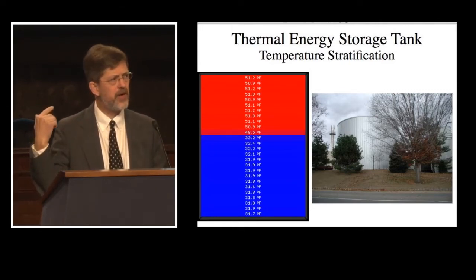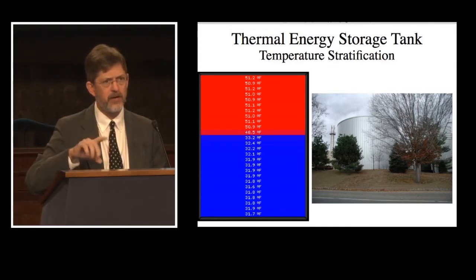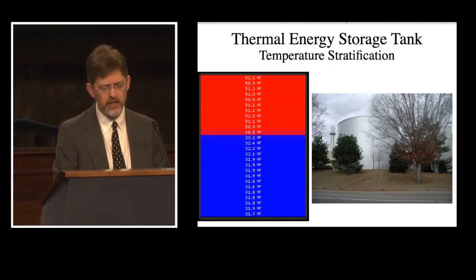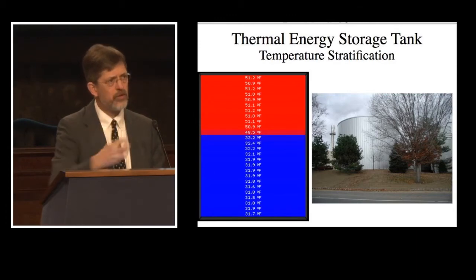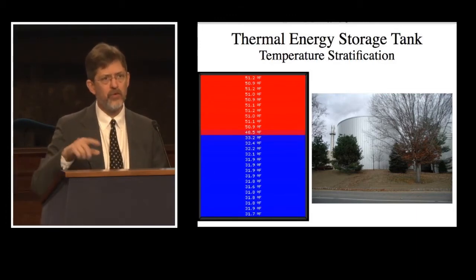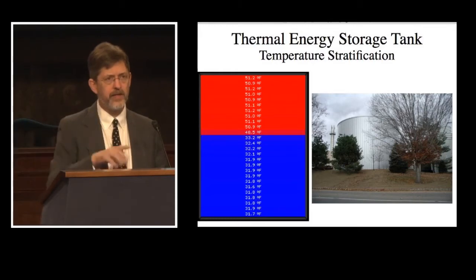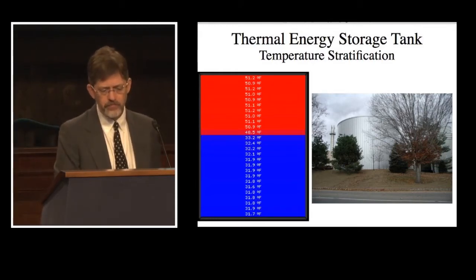You can see it's thermally stratified. The cold water's denser, it sits on the bottom. The warm water is less dense, it sits on the top. So to deliver cooling, we pump out of the bottom. To recool the tank, we pump cold water back into the bottom and displace the warm water.